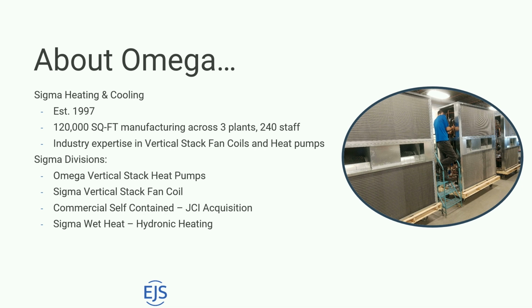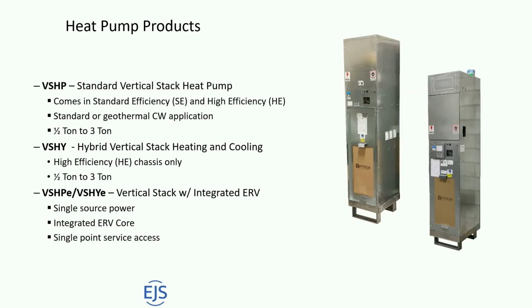They also make a vertical stack fan coil, right? So from a perspective of vertical stack arrangement, you can do the same thing without a compressor, and it's a fan coil with cold water and hot water. Again, 2 pipes. Everybody's trying to save money, so 2 pipes throughout the building, and now you add the geothermal portion to it, you get that incentive from a tax credit, but you also get the incentive of exchanging heat from one side of the building to the other. So we have a couple different versions of the heat pumps, right?